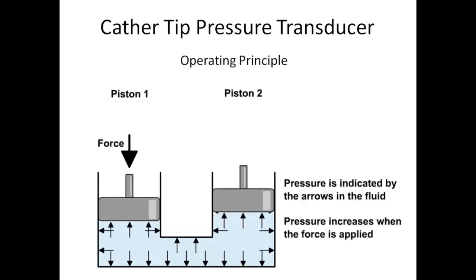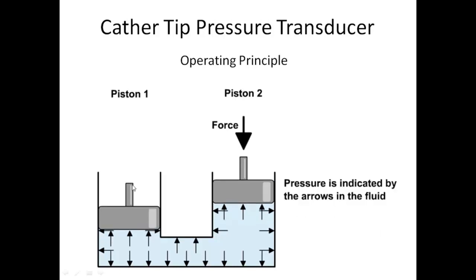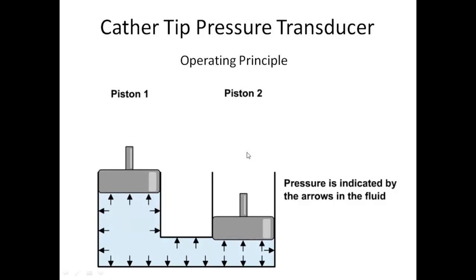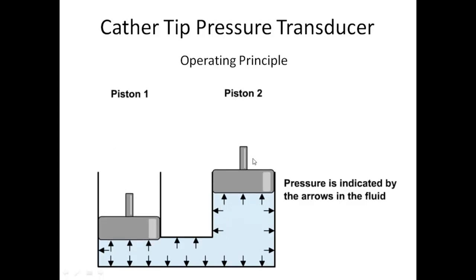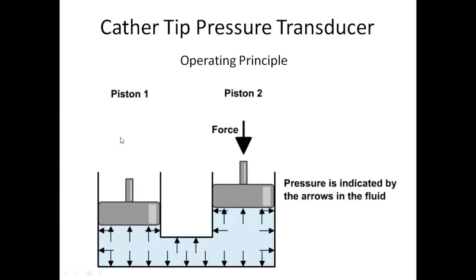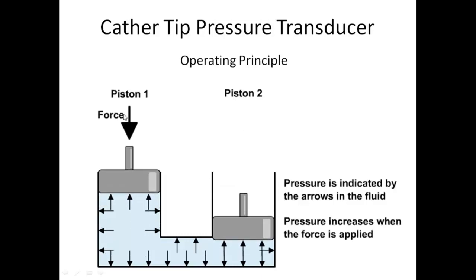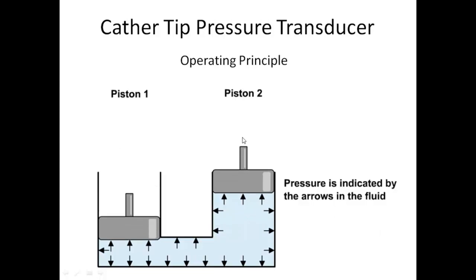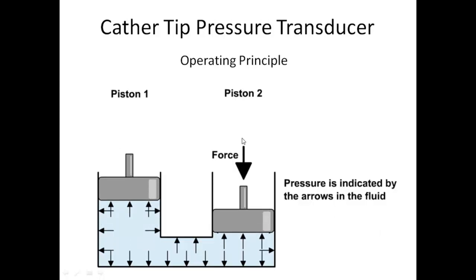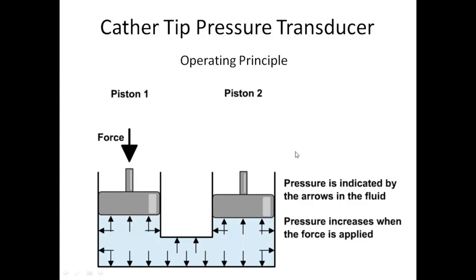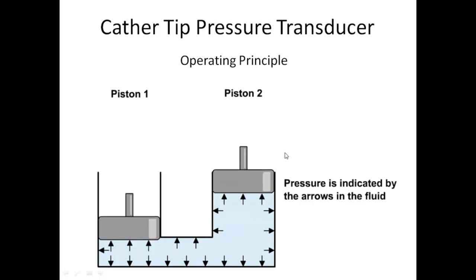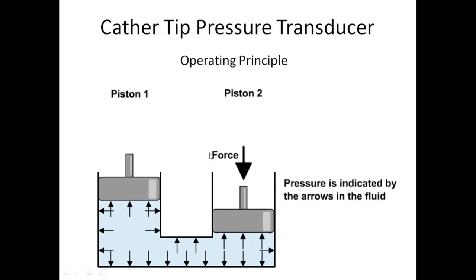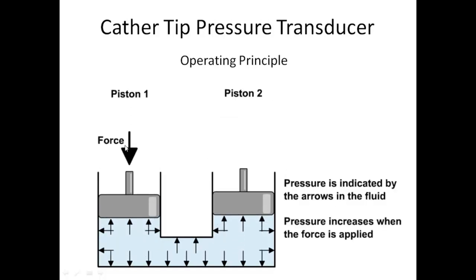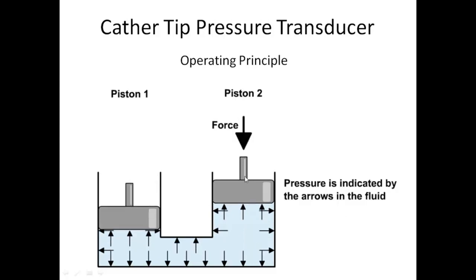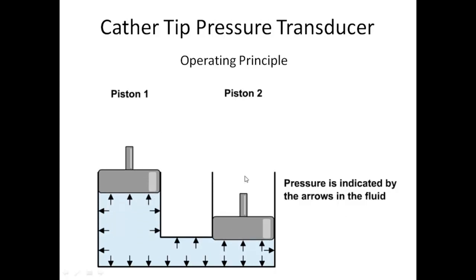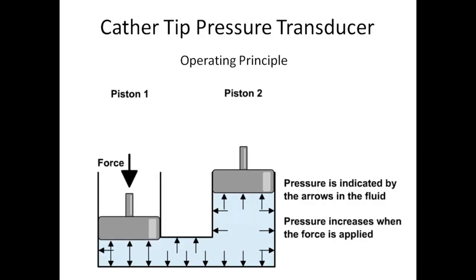From one side, if I press, you can consider the first side as one end of the catheter, and this piston 2 is actually the other end of the catheter. So if the wall of any heart valve exerts a pressure, this goes down, and the other end will bulge out, it will be rising. If I attach a piezoelectric crystal at this piston 2, what will happen when I exert force from here? The same force is exerted outwards from this side, and the piezoelectric crystal will capture that force and give you a voltage signal, right?